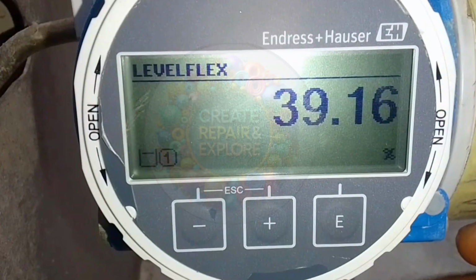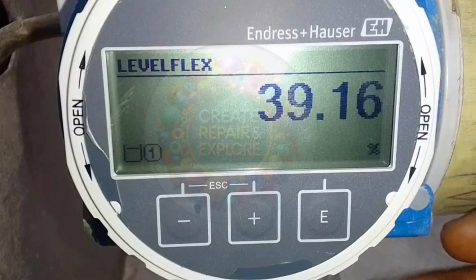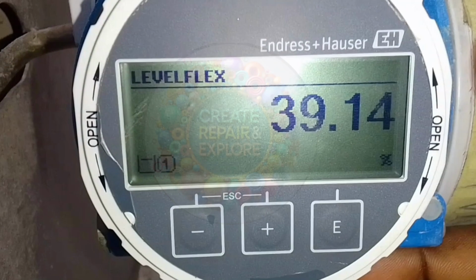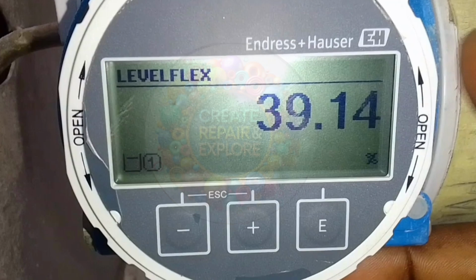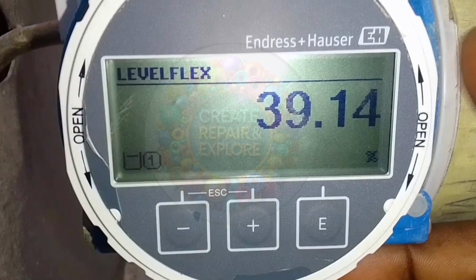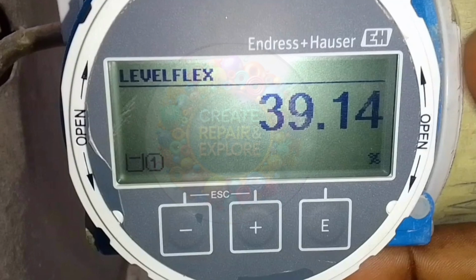This level probe is showing 39%, and as you can see, there is nothing in the tank where it is positioned. So this is a false reading, and as such it needs calibration. So we're going to be using the mapping feature to calibrate this probe so that we get the actual reading.